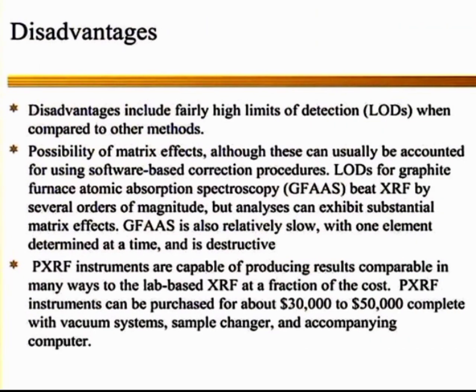Next, disadvantage of XRF. Disadvantages include fairly high limits of detection (LODs) when compared to other methods. Possibility of matrix effect, although this can usually be accounted for using software-based correction procedures. LODs of graphite furnace atomic absorption spectroscopy (GFAAS) beat XRF by several orders of magnitude, but analysis can exhibit substantial matrix effects.